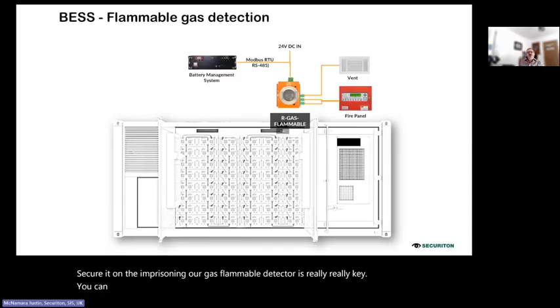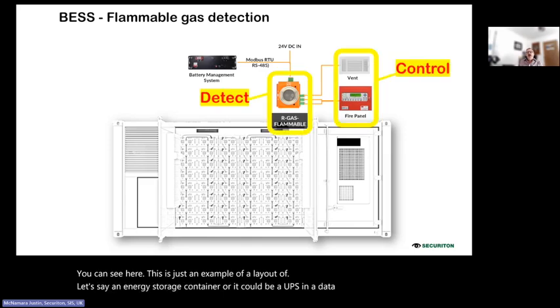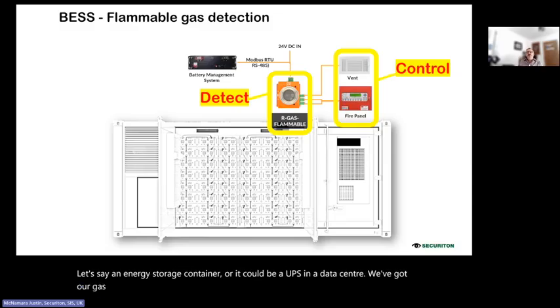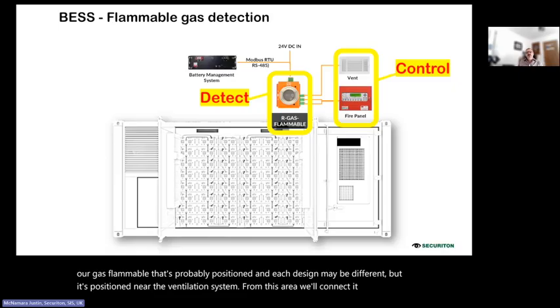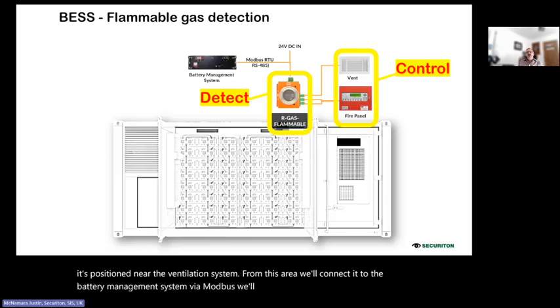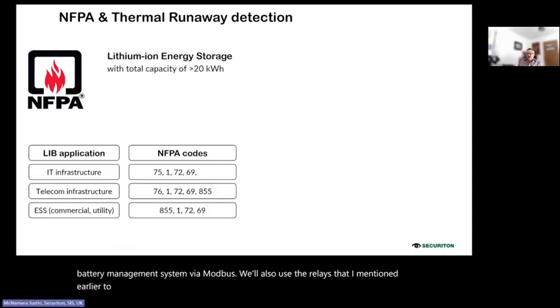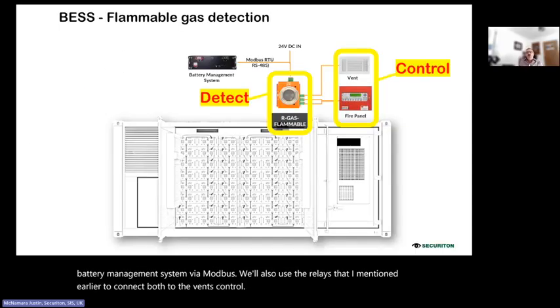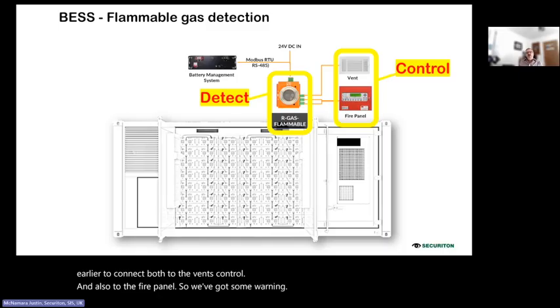You can see here, this is just an example of a layout of, let's say, an energy storage container, or it could be a UPS in a data center. We've got our gas flammable detector that's probably positioned, and each design may be different, but it's positioned near the ventilation system from this area. We'll connect it to the battery management system via Modbus. We'll also use the relays that I mentioned earlier to connect both to the vent control and also to the fire panel. So we've got some warning, we've got some control, and that will enable further actions to be taken.